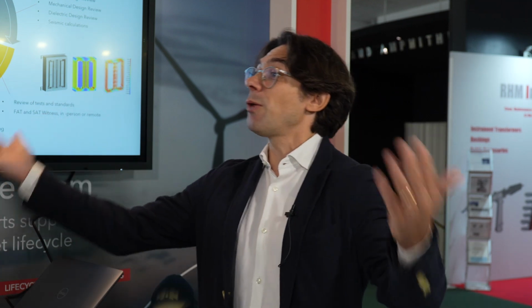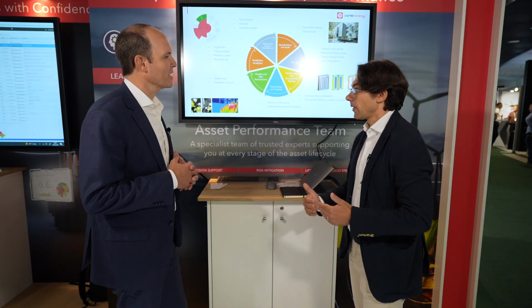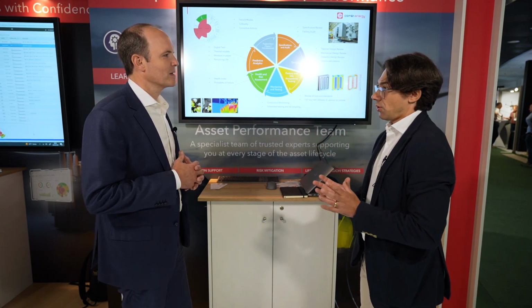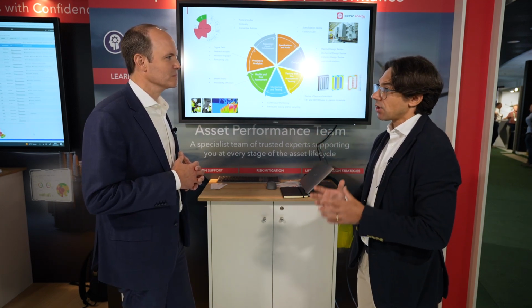Because when the transformer is in the field, it's affected by loading conditions, temperatures, harmonics, voltage transients, true faults - this is the first cause of failure of transformers. Transformers fail because of outside events. Right, so this is where the monitors...